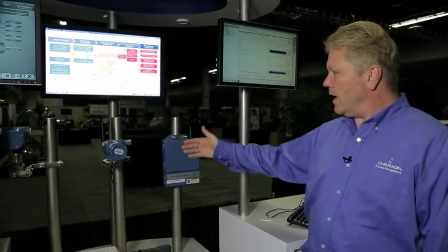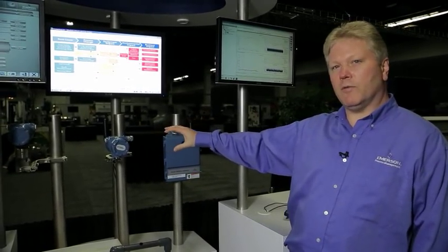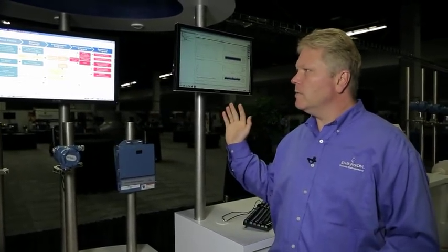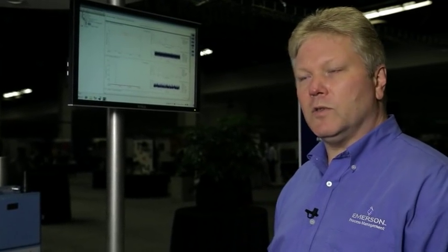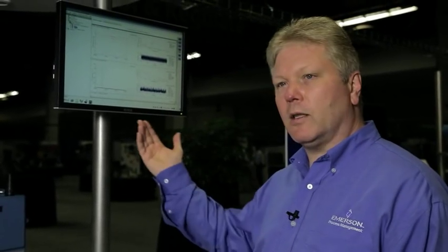So instead of having people run around manually checking to get information, what we have is this vibration transmitter that goes to the gateway, and the information coming from there I can send to two different locations. The information is valuable to both maintenance and operations. For maintenance, I have a lot more detailed information, and the benefit is that they can predict and plan for condition-based maintenance. If the pump has its normal wear and tear and degradation, they can predict and plan on a normal schedule when they need to have maintenance for that pump.